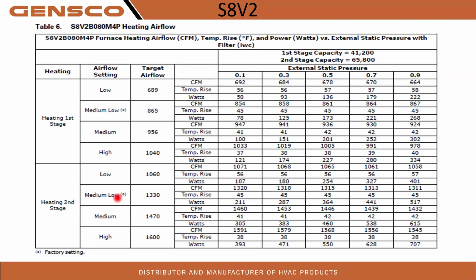And then our high speed, medium low. Again, we can change these settings. At 0.5 is 1315. This is our minimum for our gas heat, by the way. So keep in mind, this is for gas heat. This is airflow for the gas heat side.